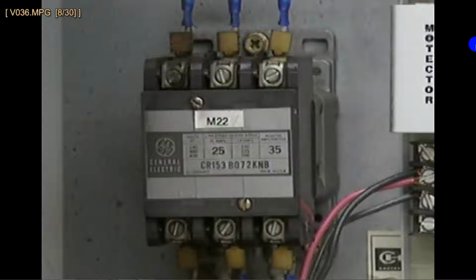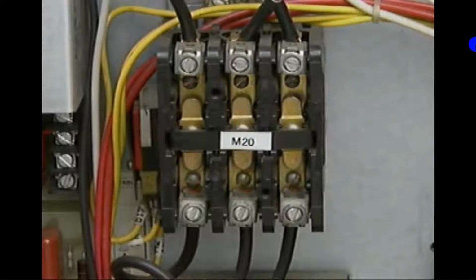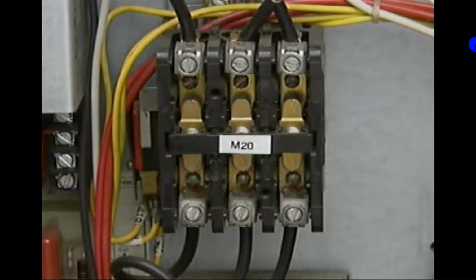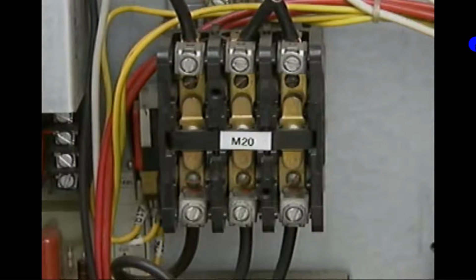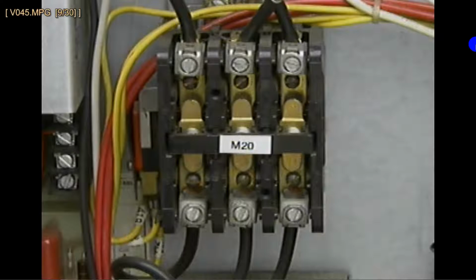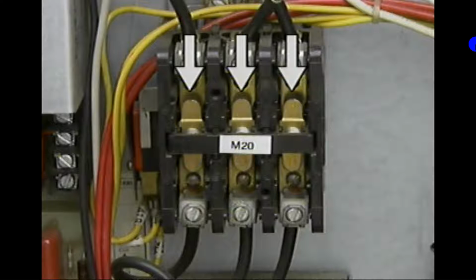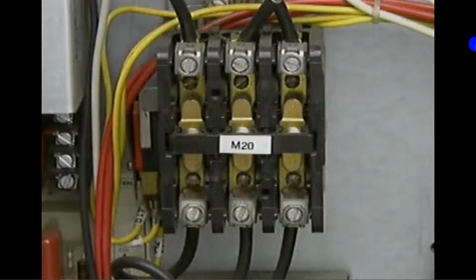In this part, we'll look at a typical magnetic contactor used in AC motor controllers and see how it operates to complete or interrupt the circuit between a power source and a motor. A magnetic contactor is a key part of any magnetic motor controller because it directly controls the power to the motor. Most magnetic contactors have 3 sets of contacts, one for each phase in a 3-phase AC circuit. A contactor may also have additional sets of contacts called auxiliary contacts.